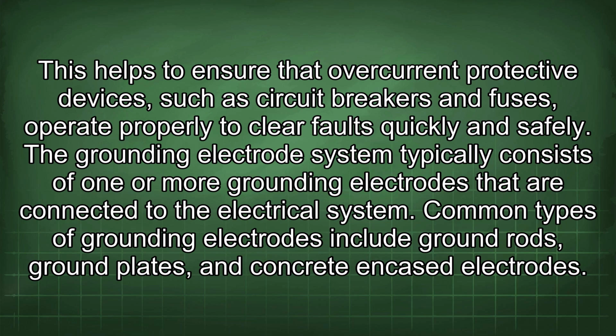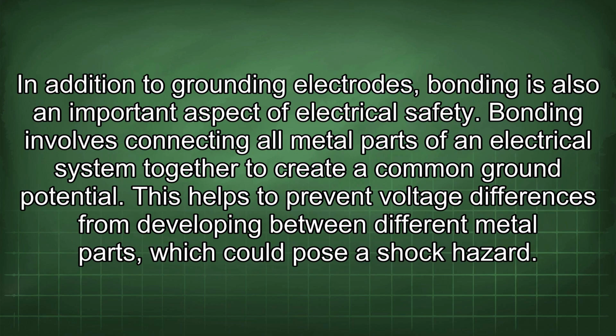The grounding electrode system typically consists of one or more grounding electrodes that are connected to the electrical system. Common types of grounding electrodes include ground rods, ground plates, and concrete encased electrodes. In addition to grounding electrodes, bonding is also an important aspect of electrical safety. Bonding involves connecting all metal parts of an electrical system together to create a common ground potential. This helps to prevent voltage differences from developing between different metal parts, which could pose a shock hazard.